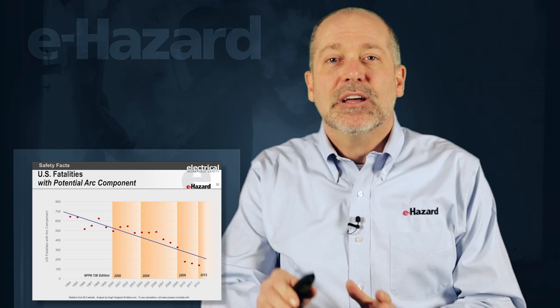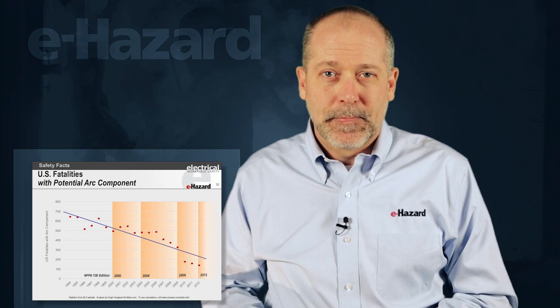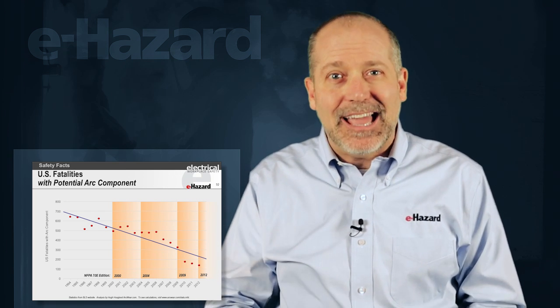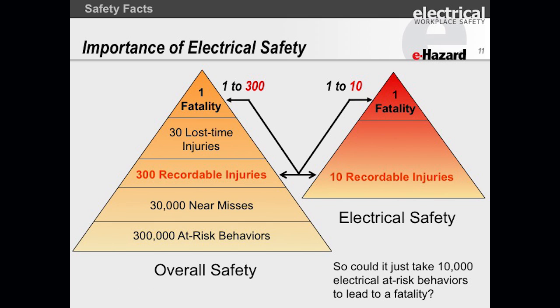The second thing that's really saved lives is having arc-rated clothing that's closely matched to the hazard. When you match it to the hazard, most people walk away with no injury or much less injury than they would have before. So we're seeing fewer people dying from arc flash because we're wearing the right PPE. That's one of the biggest changes that have come about.